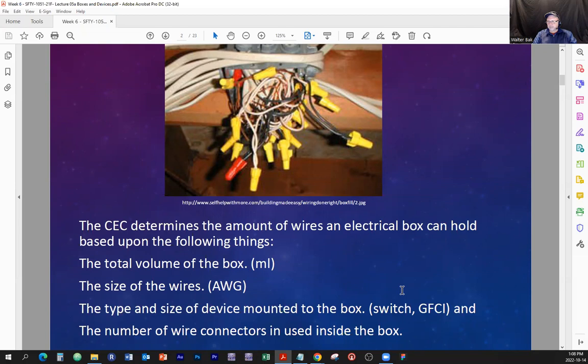And there's only one pathway. So whatever leaves goes through the load and comes back on the neutral. There is no other way for the current to flow. So the current flowing out has to be equal to the current flowing in, and that's what the GFCI circuitry measures. If there is any deviation from that, then some of the current did not make it back to the neutral, which means that some of the current escaped to the ground, usually through the device box. Maybe some water got in it and the water is conductive, so some of the current flows through the water and goes into the ground through the device box that is grounded.